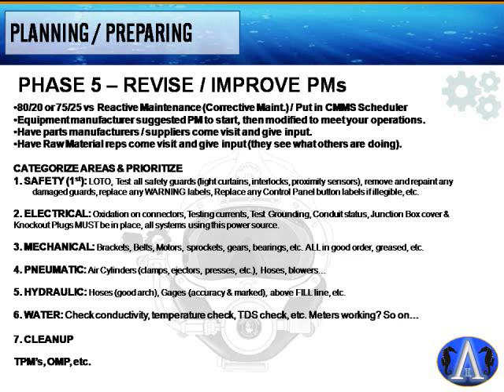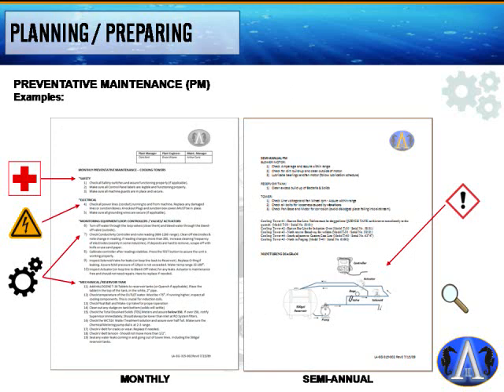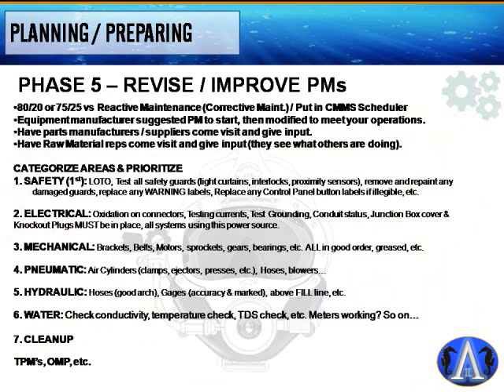Categorize and prioritize PMs. Safety always comes first: test lockout/tagout, all safety guards like curtains, interlocks, and proximity sensors; repaint damaged guards; replace worn warning labels and control panel button labels — this is OSHA-required. A good practice is to have technicians clean an area first so any leaks stand out clearly if they aren't already obvious.